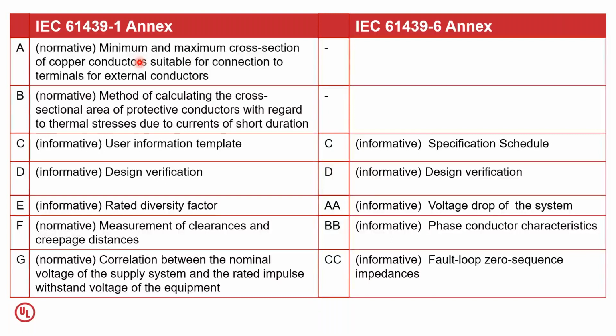If I have to do a test, then quite naturally I need to know the cross section of the copper conductors that I have to select based on the rating of the busway the manufacturer has declared. Without this information, I would be unable to choose the right cross section for my testing purpose. That is why this is mandatory, or considered normative. Then you have another normative section: a method for calculating the cross-sectional area of protective conductors. This is again mandatory in terms of constructional requirement. Then finally you have a couple of informative sections.